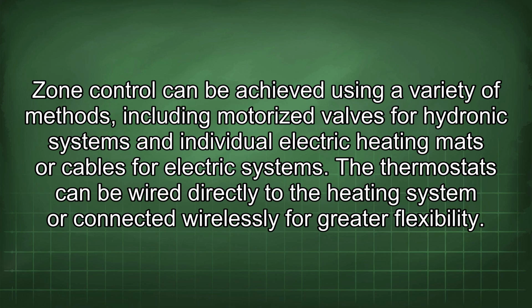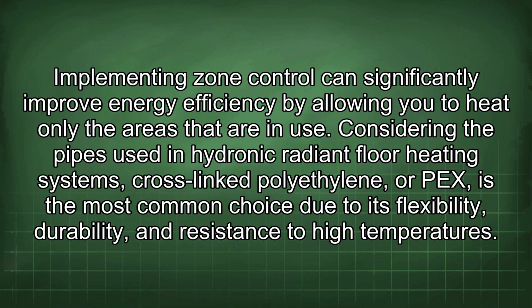The thermostats can be wired directly to the heating system or connected wirelessly for greater flexibility. Implementing zone control can significantly improve energy efficiency by allowing you to heat only the areas that are in use. Considering the pipes used in hydronic radiant floor heating systems, cross-linked polyethylene, or PEX, is the most common choice due to its flexibility, durability, and resistance to high temperatures.